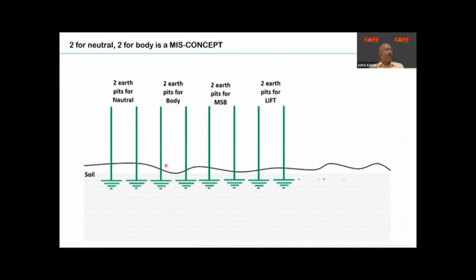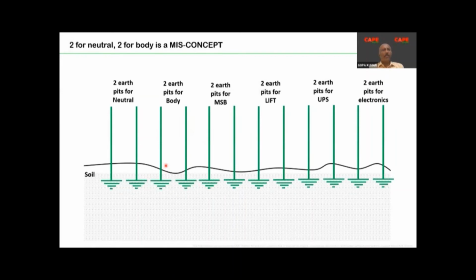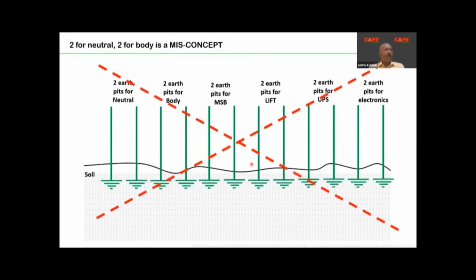If you find this kind of an installation, like two separate pits for neutral, two for body, two for lift, two for main distribution board, two for UPS, an engineer who has designed an electrical system in this fashion is not an electrical engineer. He can be called a fire engineer or fire igniting engineer, because this is the reason for fire. If you look at 100 hospitals, I'm sure that probably the majority has at least some sections like this. So please avoid it. This is never written in the standard or regulations. This is absolutely wrong, totally wrong.